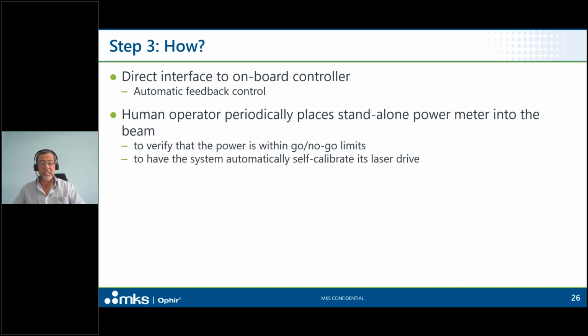Alternatively, in some applications where the expected drifts in those critical laser parameters are slower, it might be enough for a human operator to simply place a handheld standalone power meter into the beam in the target space once a day, once a month, whatever. That would need to be worked out to verify that the power is within go, no-go limits, or once every X, just to have the system automatically self-calibrate its laser drive, or make sure that there hasn't been enough degradation over time that it's time for preventive maintenance, and so on.